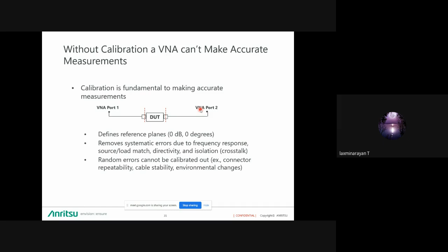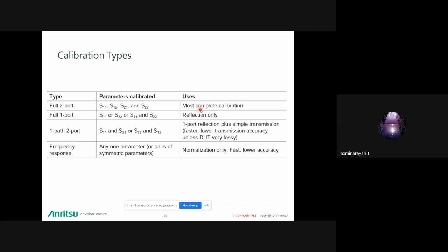When you come to the calibration types, we have a full 2-port calibration, which will cover all 4 S parameters. Most calibration is done using a full 2-port calibration. And there is full 1-port calibration, which covers only the reflection parameters. When you are measuring antennas, you can use the reflection parameters with a full 1-port calibration, do the calibration, and measure the device. And there is a 1-path 2-port calibration, which is used for simple transmission measurement, where you want to measure gain or loss. Frequency response is equivalent to a transmission measurement, used to measure loss or gain, but it has lower accuracy and is fast in time.